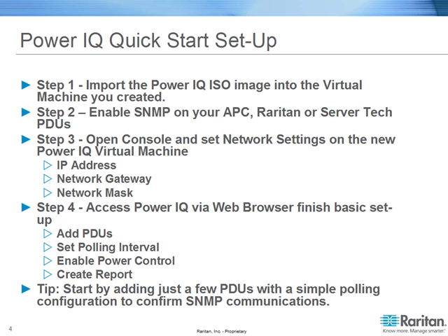Tip is to start adding just a few PDUs at a time with a simple polling configuration to confirm your SNMP communications and ensure PowerIQ is correctly pulling data from the PDUs that you want to manage. The remainder of this video will start with Step 2 and walk through Step 4.